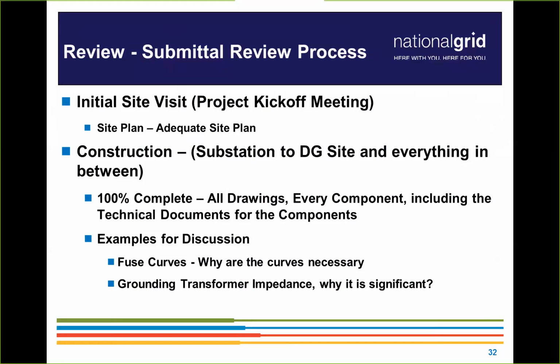So an entire project can be held up on a simple technical document. And I wanted to have Chris just discuss a little bit, for example, fuse curves and grounding transformers. So Chris? Yeah, so those two items seem to be, and then you could throw reactors in there with the grounding transformers, those three items are very critical to the acceptance of a final design.